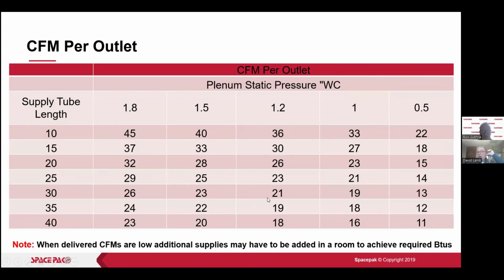All right, the CFM per outlet. This is not really on as far as the numbers, but it gives you a good idea of the differences in length and the differences in plenum pressure and what those differences cause. Here you have less pressure, here more pressure, so less CFM and more CFM. We want an adequate amount of pressure, but not too much, or we're going to be pushing the air out too quickly and working the motor too hard.